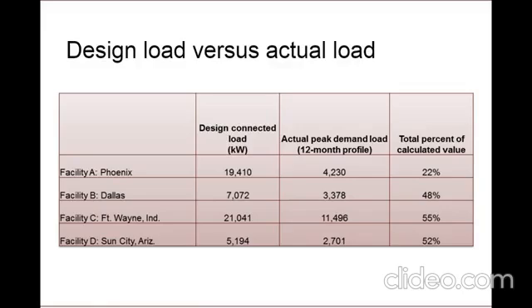Yeah, as you can see from Rob's example, what the code required those original engineers to calculate on paper can be drastically different from what the facility actually runs in real life. So I've started an internal database where we try to get our engineers to complete, at the end of the project, the information on the total connected design load. Then we challenge them to obtain reports back from the facility at least 12 months after the facility has been operating to obtain that real data from the utility company on what their peak demand was over that past 12-month period. So this table you see here is just a sampling from that database, but as you can see, the values can vary greatly, ranging anywhere from only 22% to 55% of the originally anticipated load. So it falls right in that range of the project that Rob was talking about at 34%.